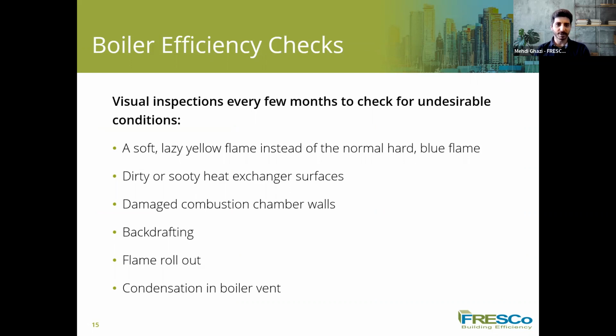So for that, as I mentioned, a visual inspection every few months is needed to check if we have any of these conditions, like a soft lazy yellow flame instead of a hard blue flame, or a dirty heat exchanger surface, or a damaged combustion chamber wall, and whether we have backdrafting or not. Backdrafting could be checked: sometimes we have white powder at the top of our boilers, below the venting flue pipe. If there is white powder, this could be a sign of backdrafting, and backdrafting is just a waste of energy, and it needs to be prevented.